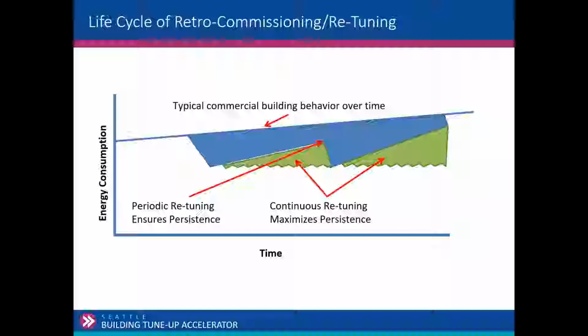So obviously continuous retuning or monitored based commissioning provides the most savings, where you're continually monitoring the buildings. But generally in smaller buildings, we don't do that. We don't have real-time. Is anybody working with any buildings that have real-time monitored based commissioning? I know, Stephen, this building has that. This building has SkySpark in there that's being monitored in real time.